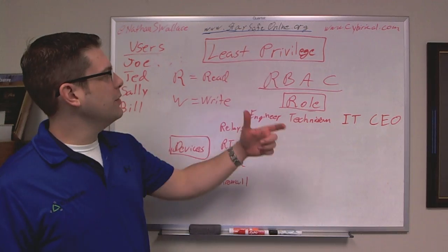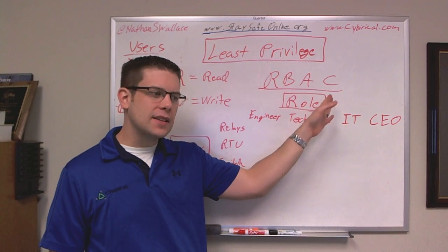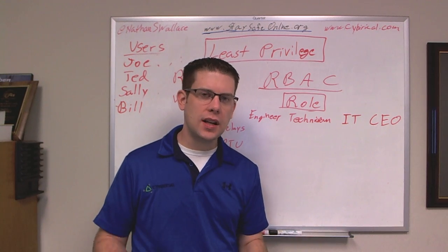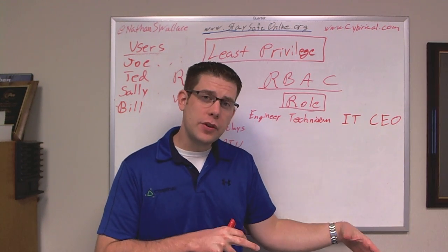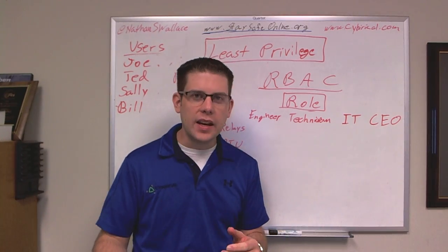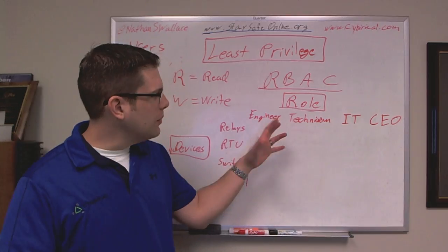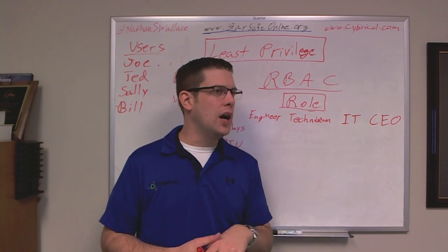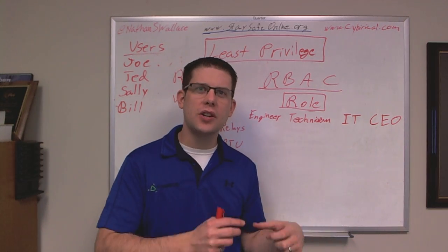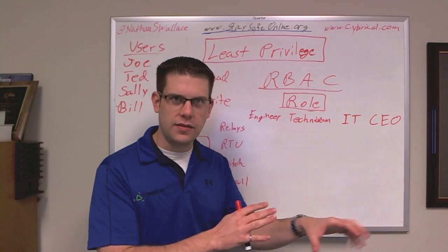So the idea of least privilege, in practice, we look at this as far as RBAC, or role-based access control. You can apply this in the context of any type of information technology, communications type infrastructure. But in the context of a control center, SCADA, supervisory control and data acquisition, or ICS, industrial control systems, and more specifically a power system, such as a substation or a power plant, you really have to have those design engineers, professionally licensed engineers, do this type of configuration because it has to be in the context of the application.